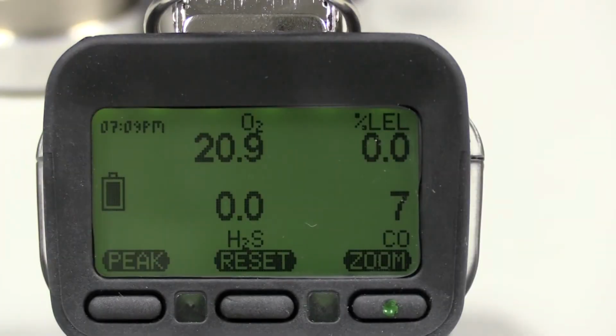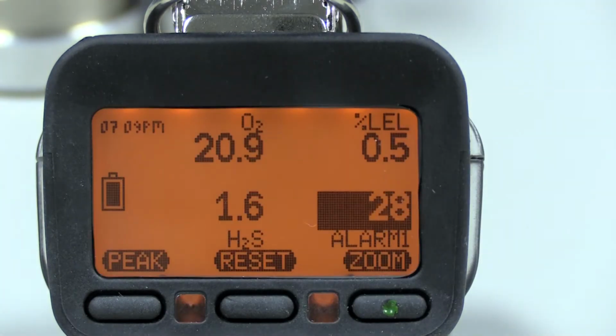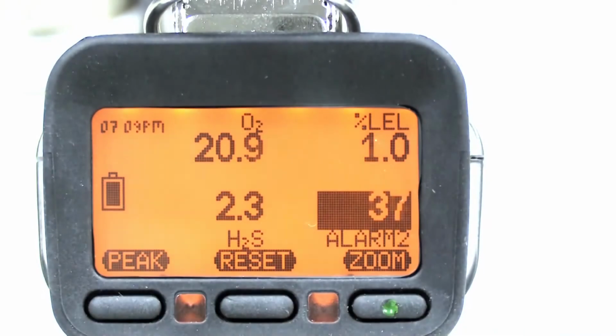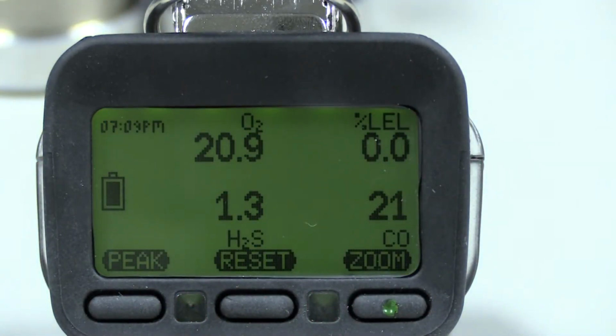In normal operation, the display shows an individual real-time reading for each sensor. If the readings of any sensor reach the alarm concentration, the audible alarm, the LED alarms, and the vibrator alarm will be activated. G450 alarms are normally self-resetting. When the readings return to safe levels, the alarms cease and the instrument returns or continues with normal operation.